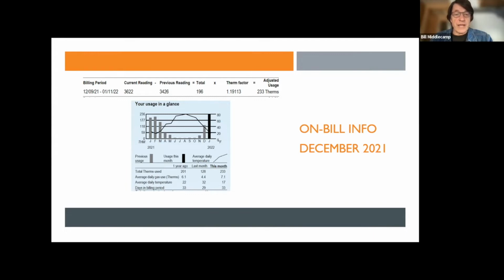The average daily temperature, 17 degrees. So again, using that heating degree day formula, you take 65 minus 17, and that comes up to 48 degrees, 48 heating degree days. And it tells you how many days are in the billing period, which is useful as well.